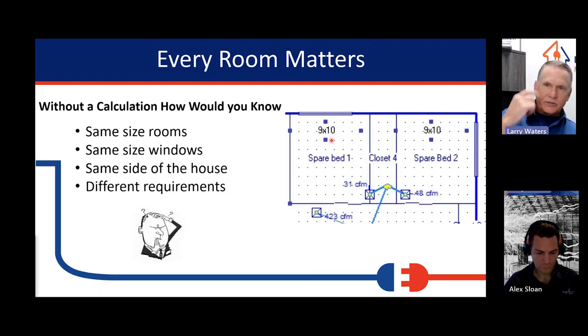So how would you know this? Another thing that we hear in the industry is "air don't care." That's something that people actually say. And the other one is "small room, small duct, big room, big duct." So what does that mean, right? If a contractor came in and said small room, small duct, big room, big duct, here we have 2 rooms that are the same size. One of them needs 50% more airflow than the other one needs. We know why by looking at this.